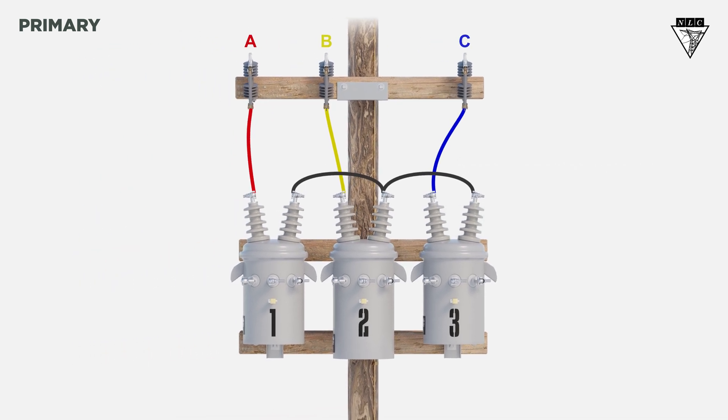Single-phase transformers with two primary bushings must be used when floating the Y-point to ensure the neutral point can adjust to the system's imbalances. Using only one primary bushing wouldn't allow this to occur.